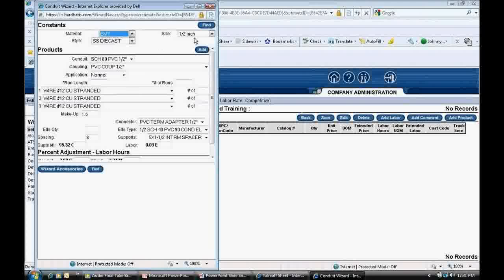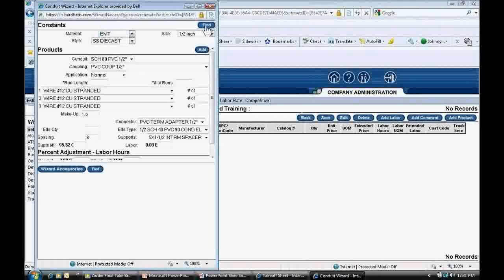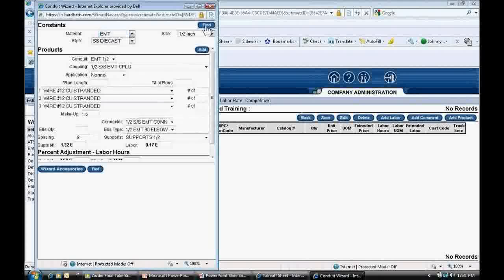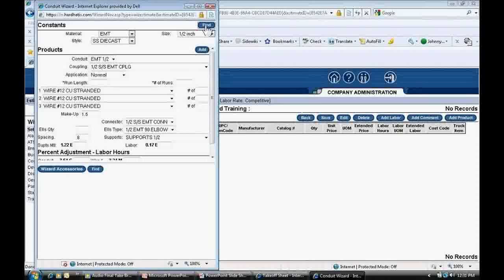This is where the conduit run information is entered from the take-off sheet. I click on the Material drop-down and select EMT. I check and see that the Size drop-down is already set at half-inch. Below the Size, it says Style. I'm going to leave the setting at SS Die Cast, which means Set Screw Die Cast Type Fittings. Next, at the top right of the pop-up, I click Find. That populates the correct material down below.